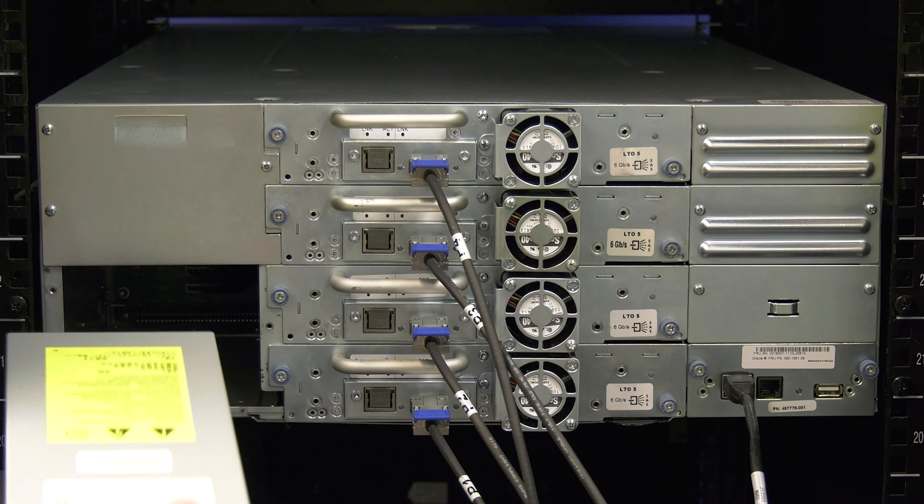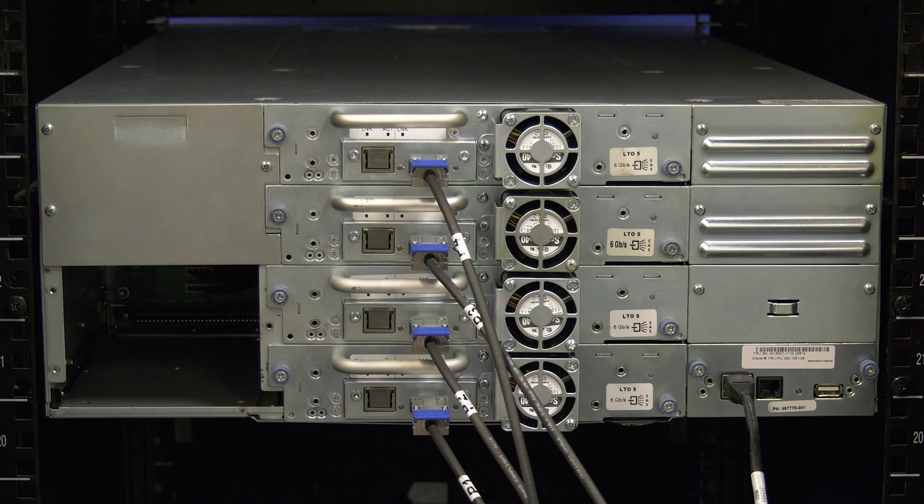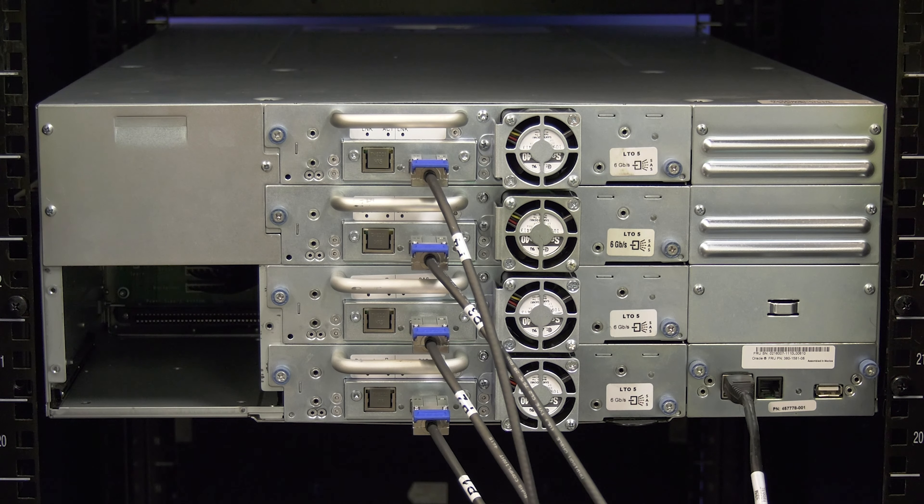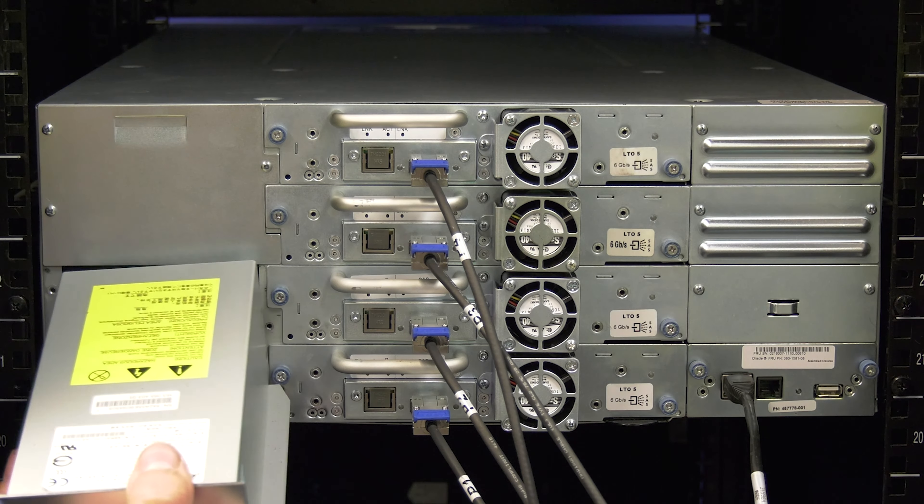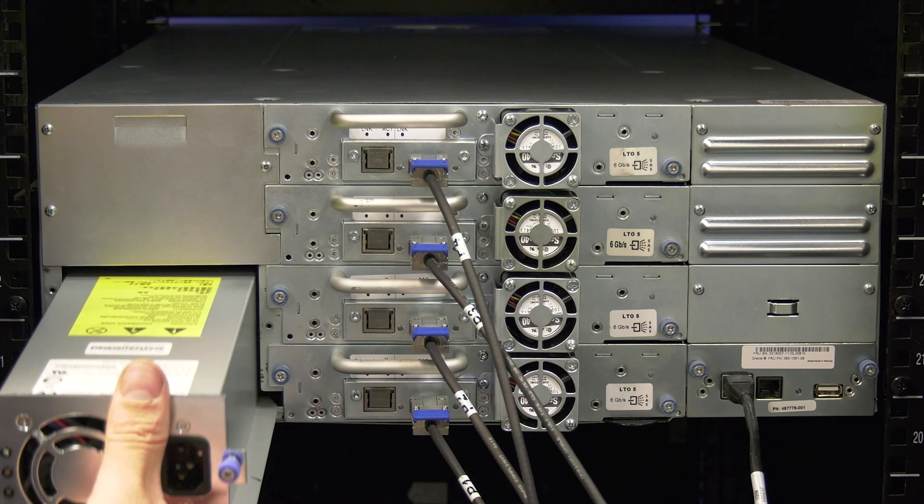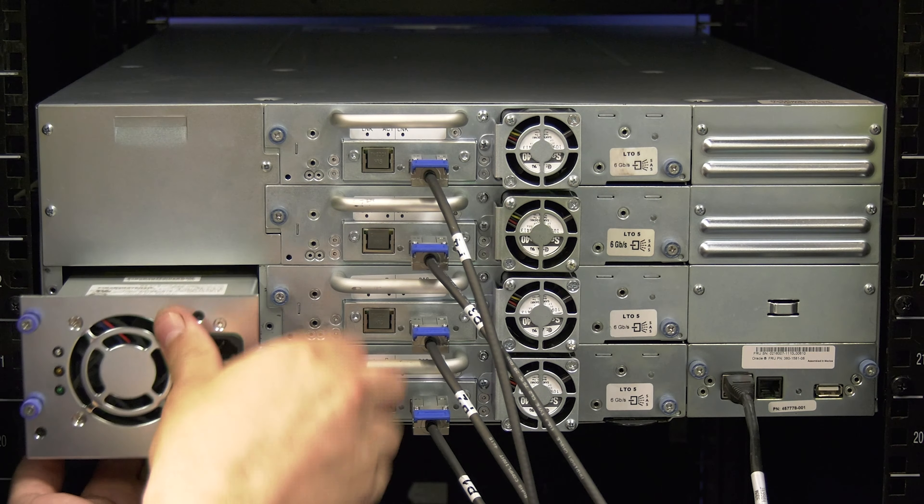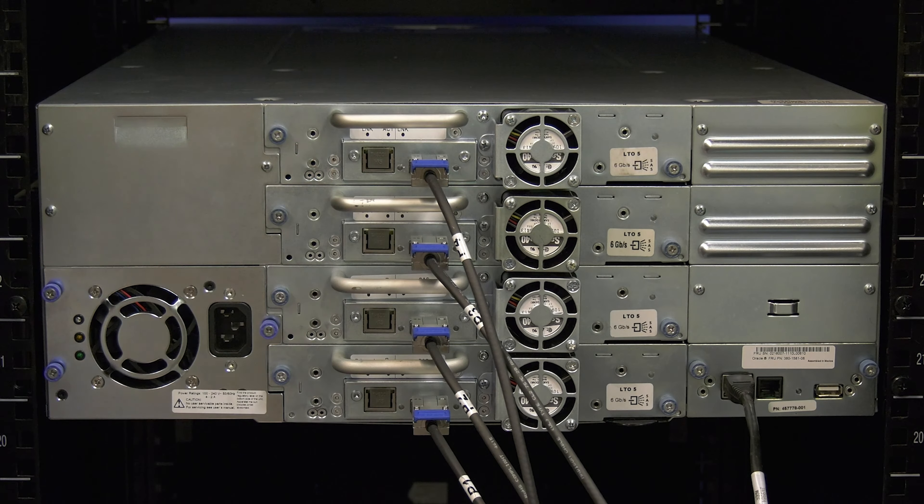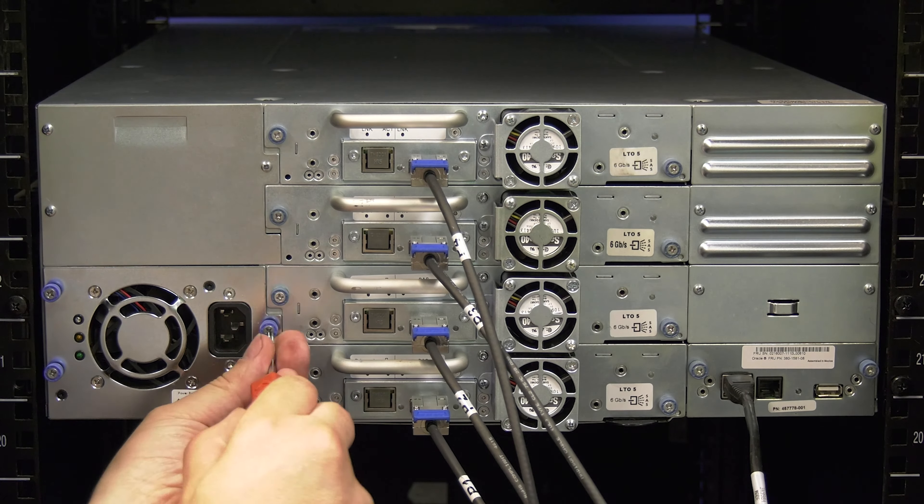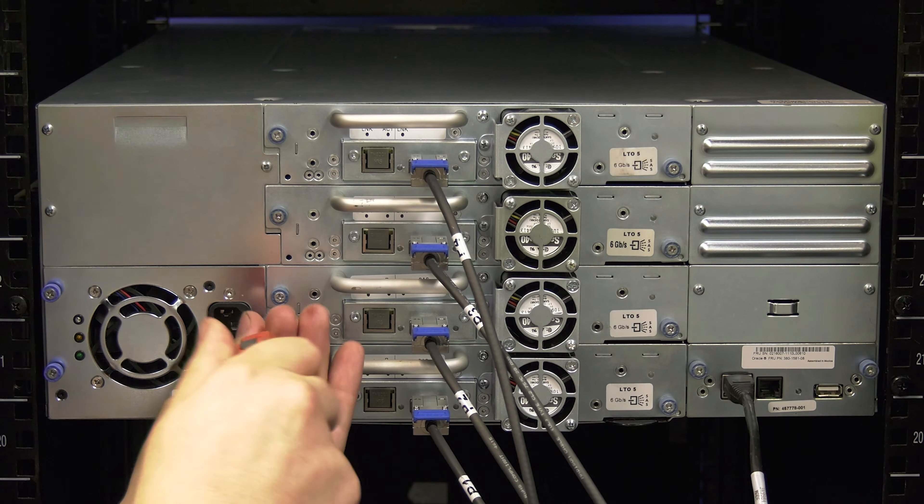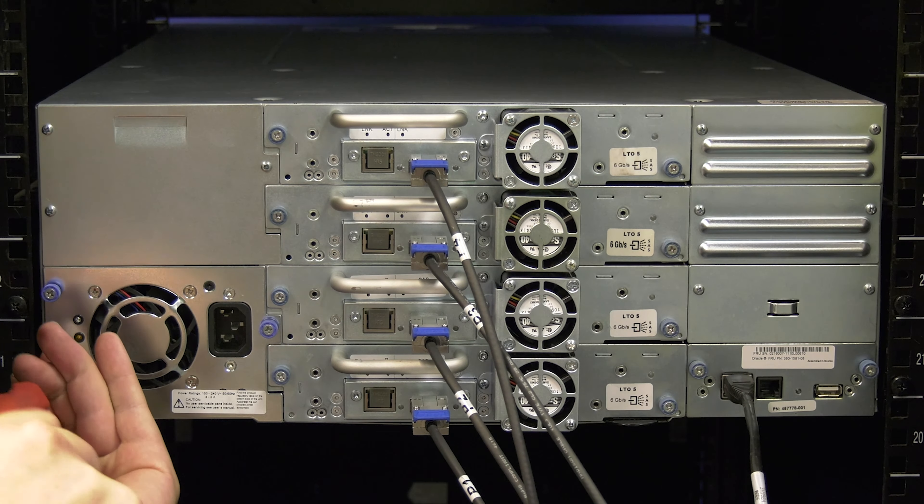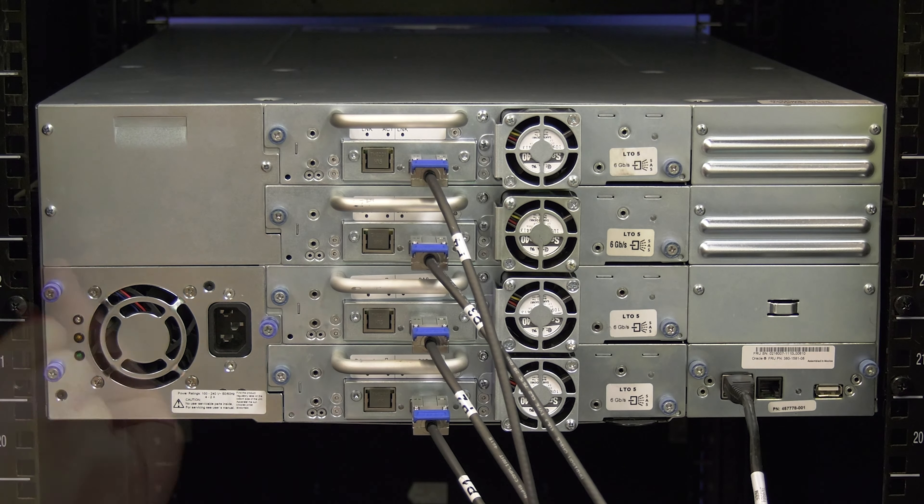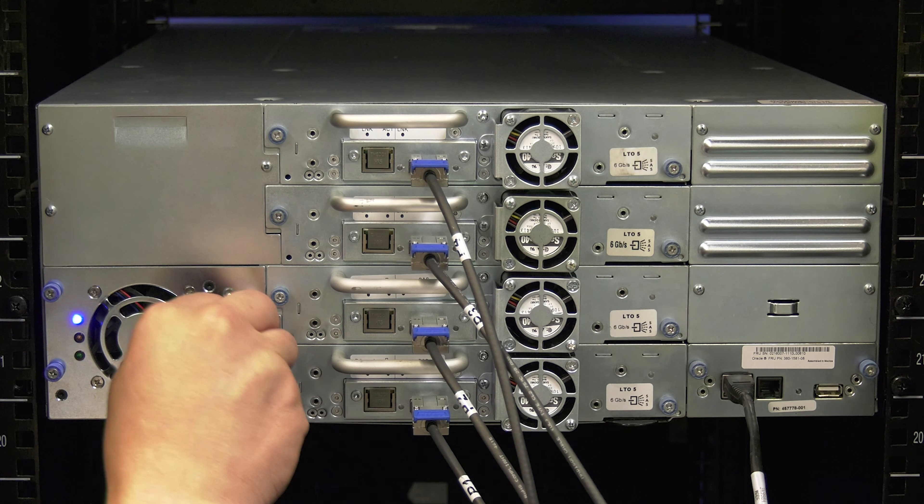Now you will install the replacement power supply. Carefully line up the supply with the guide rails in the empty power supply bay and push the supply in firmly until it is fully seated. Then, tighten down all three thumb screws and reinstall the power cord in the supply.